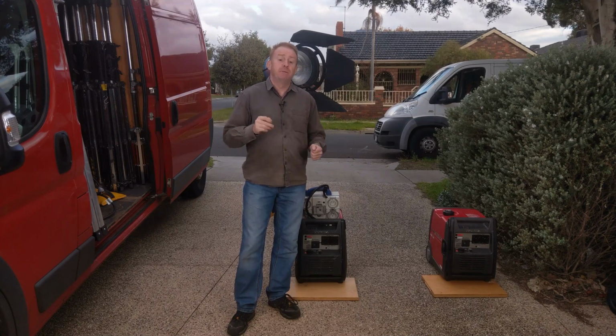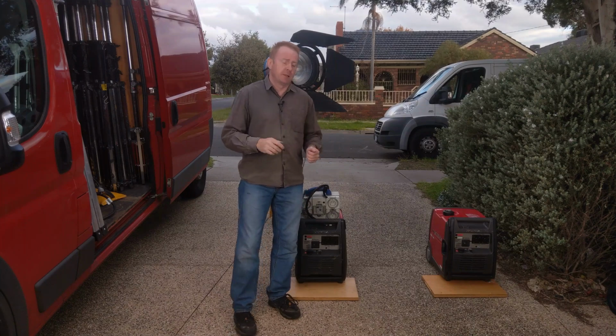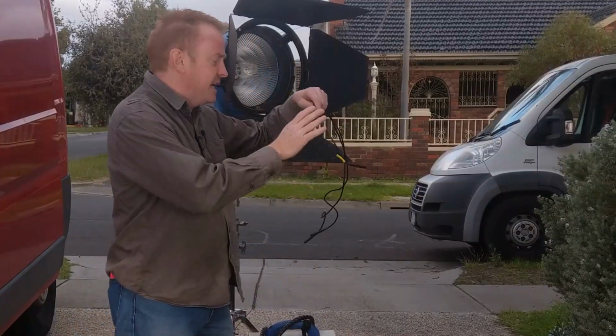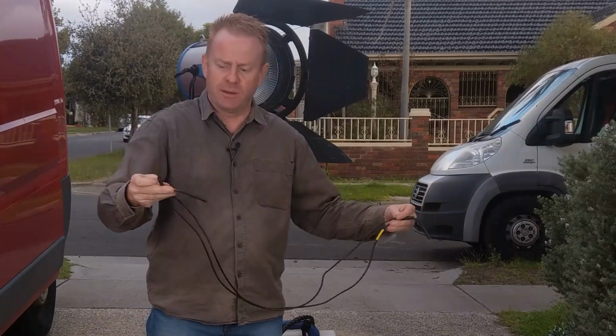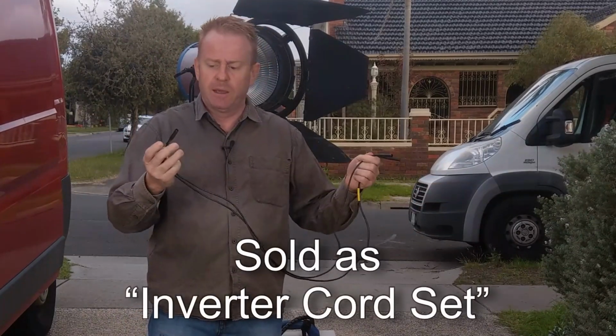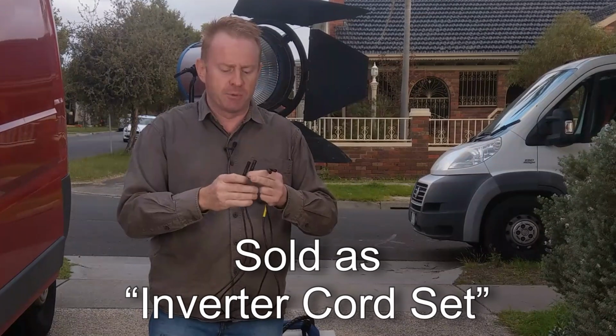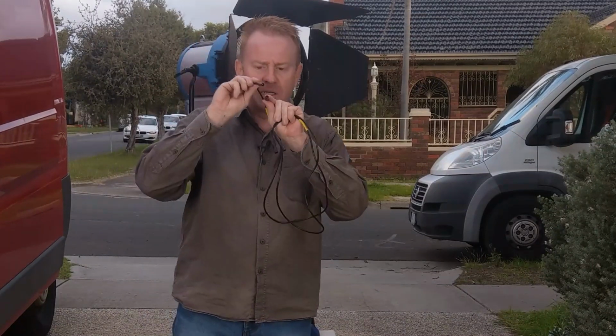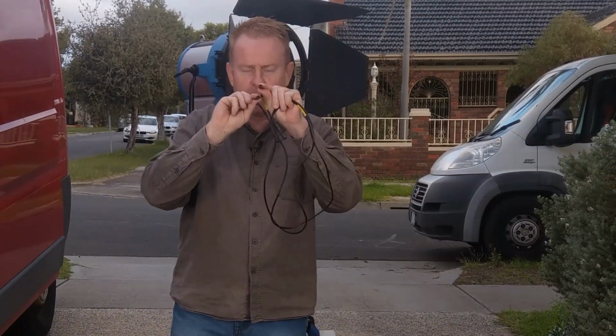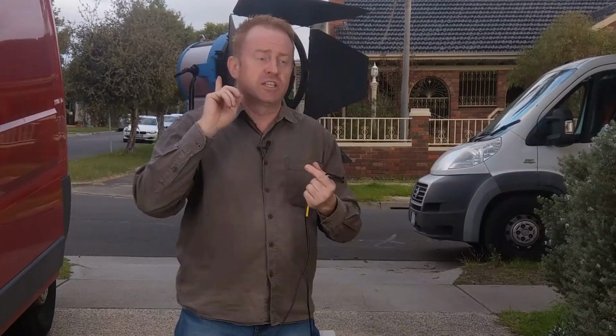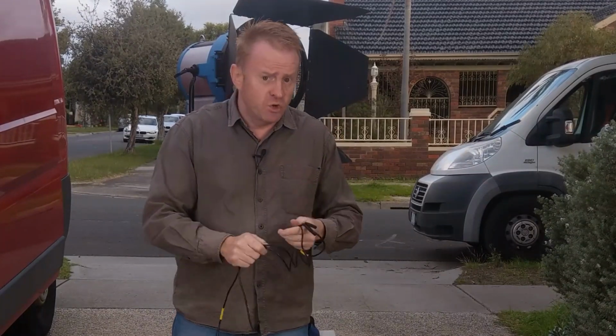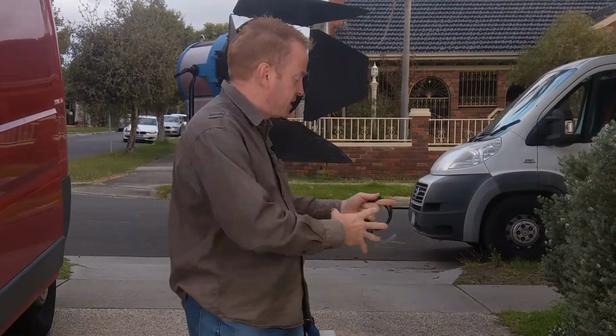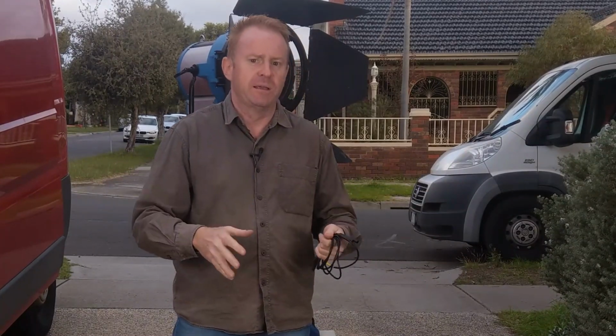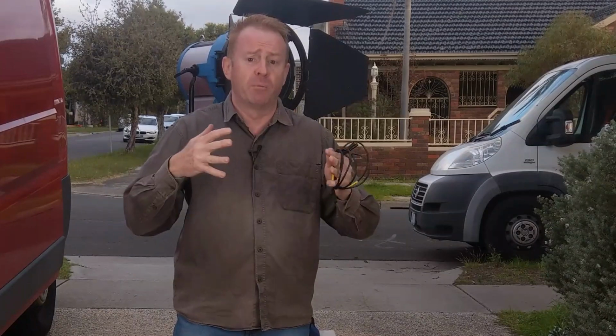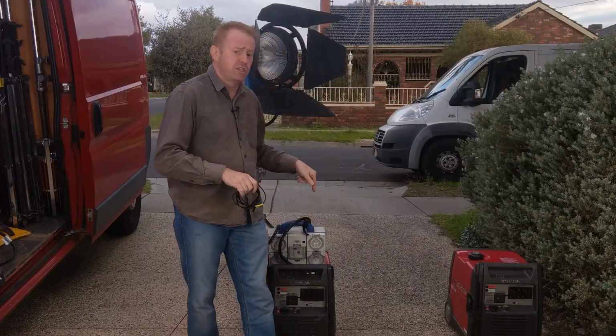Now plug in the link before you turn the generators on. That's very important. Now there are two types of links you'll come across. Standard link cable like this. I think this is called inverter link cable. With these cables, it doesn't matter which way you plug them into the generator, in terms of that way up or that way up. Makes no difference at all. Now, just to clarify that, that's if it's a floating neutral generator, which if you've just taken it out of the box from Honda, that's what it'll be, which means that the earth and the neutral are not bonded together, not connected inside the generator.